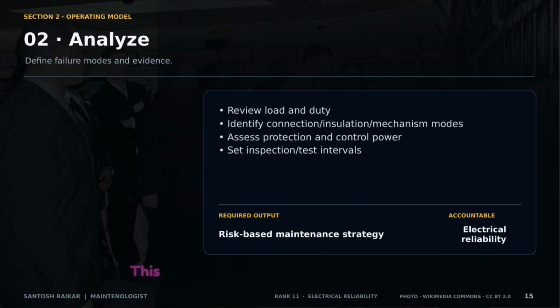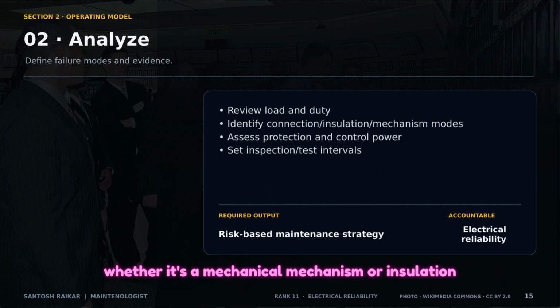Phase 2 is analysis. This is where the electrical reliability team defines the specific failure modes for each asset, whether it's a mechanical mechanism or insulation breakdown, and sets the appropriate inspection intervals based on the level of risk.